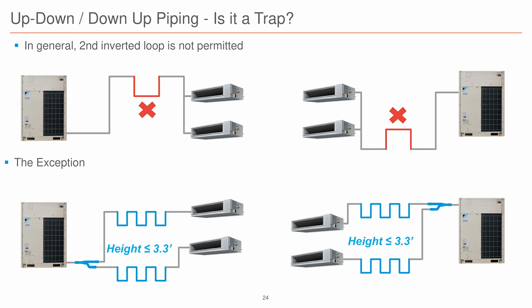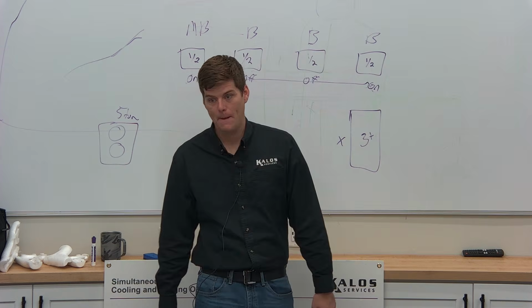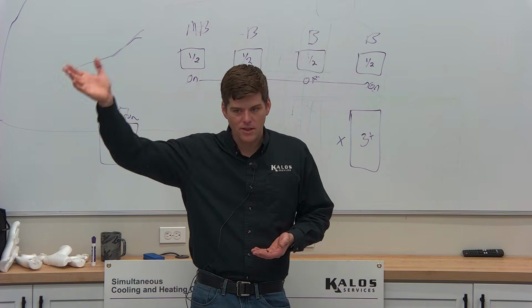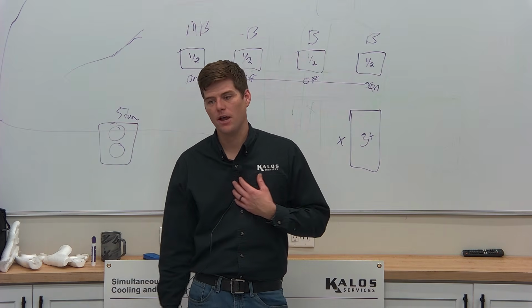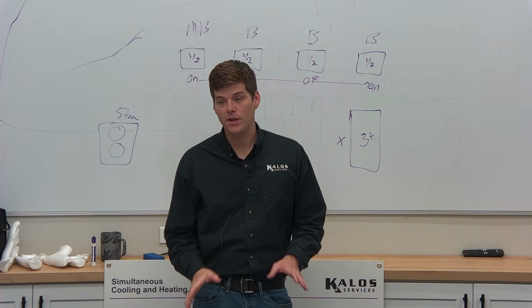Traps were put in back in the day on split systems with vertical risers to help push that oil back up to the outdoor unit, right? Or to keep oil from trapping inside the indoor unit and making it back to the outdoor unit if it was higher. It's not needed on VRF.